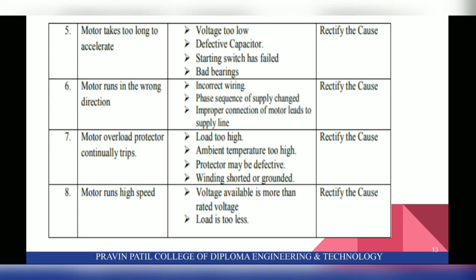Next trouble is motor runs at high speed, and causes for these troubles are voltage available is more than rated voltage, load is too less, and suggested correction is rectify the cause.